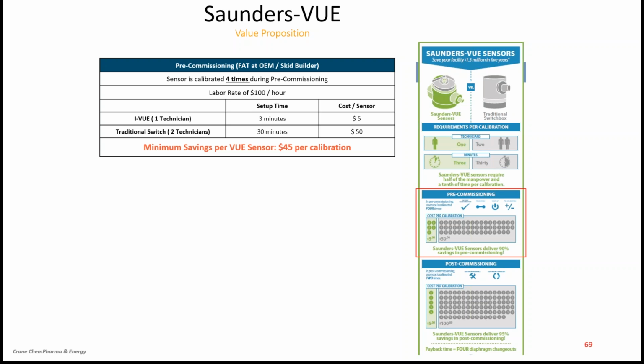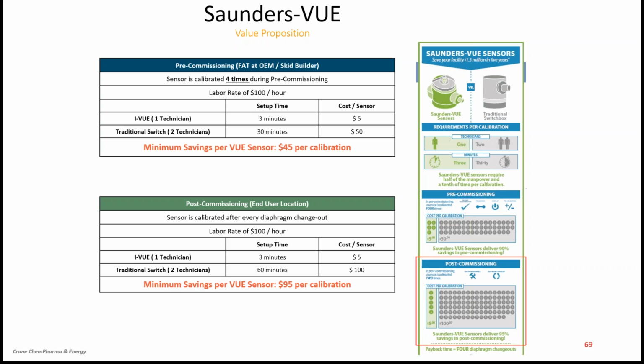So if you go to the next one, you will see in pre-commissioning, we have 4 types of calibrations, or we calibrate a switch 4 times. We calibrate it during passivation, startup, pre-calibration, and then actual running. So if you start multiplying, you will see every time you calibrate a sensor, there's a saving of $45 per calibration. Now multiply that by the thousands of sensors you have in the field, and quickly you are talking about big numbers here. So this is in the pre-commissioning stage.